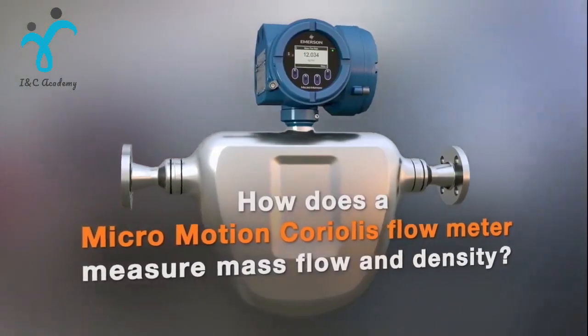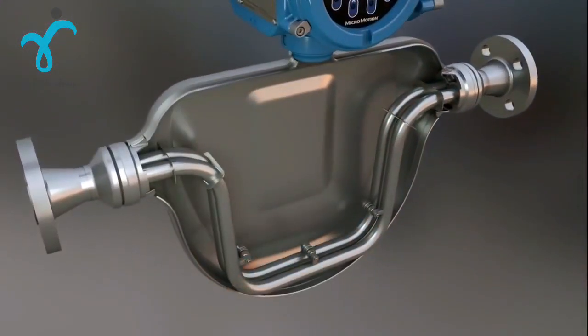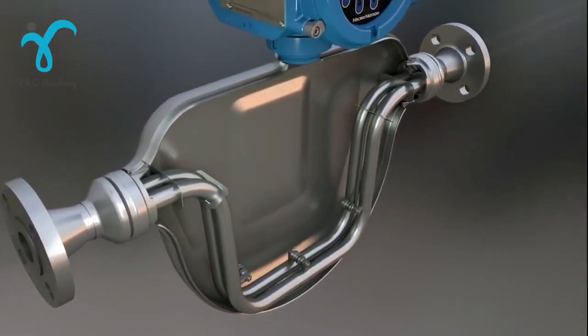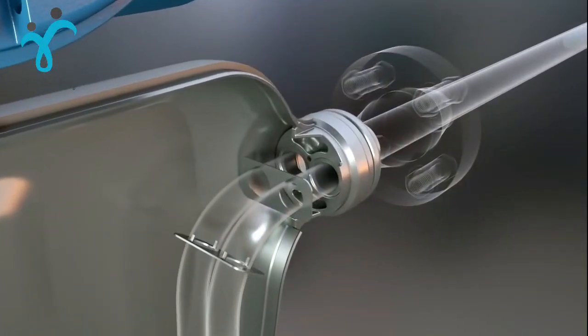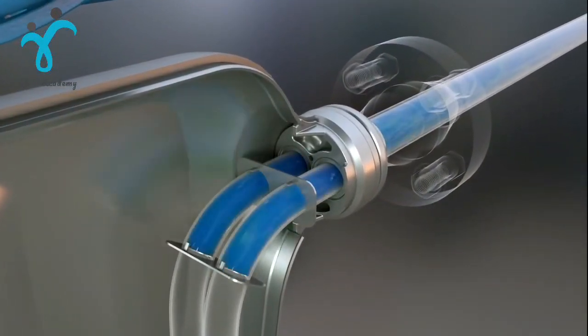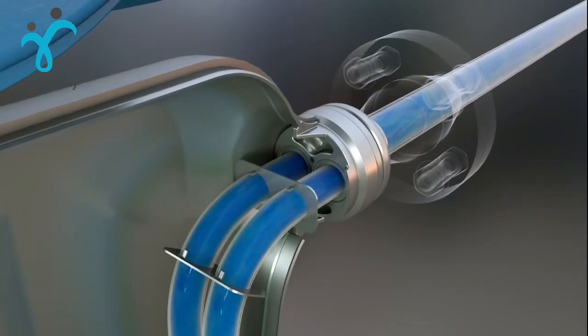measure mass flow and density. The flow meter has dual parallel flow tubes. When the process fluid enters the sensor, it is split. Half of the fluid passes through each tube.